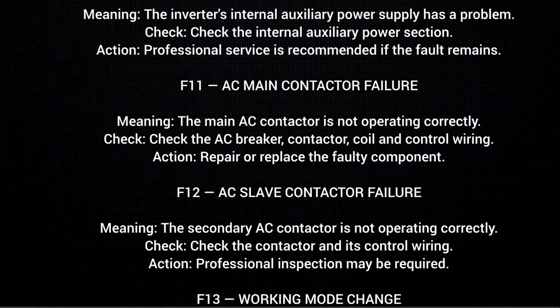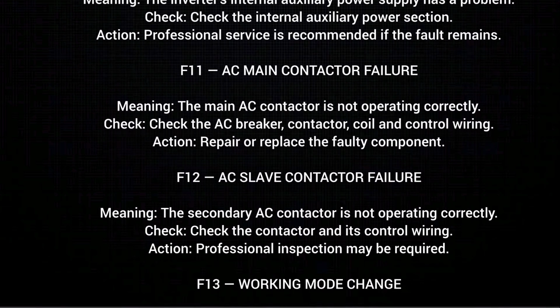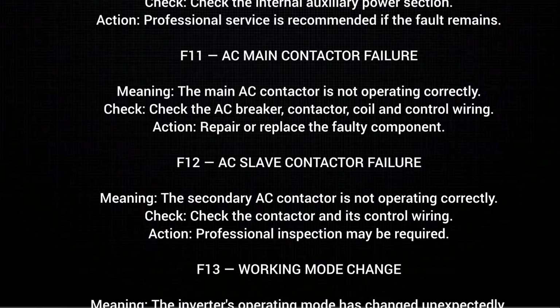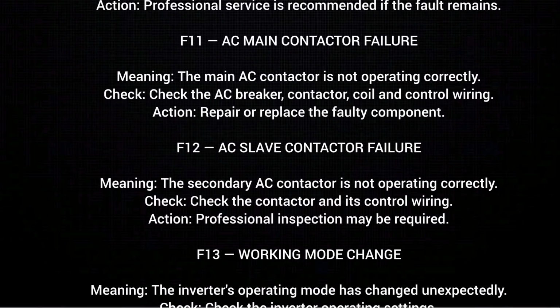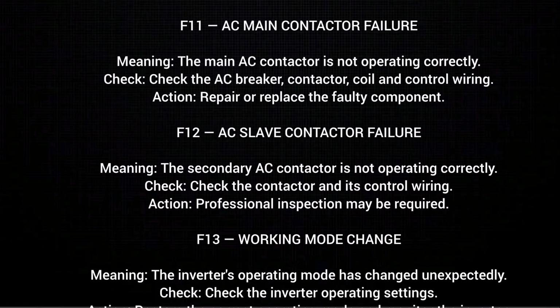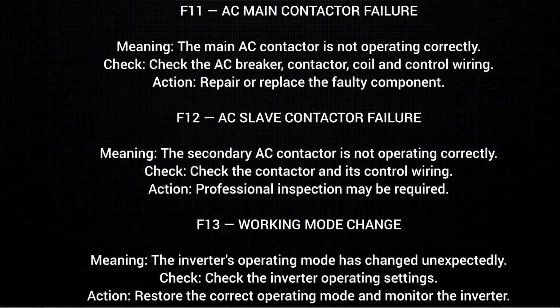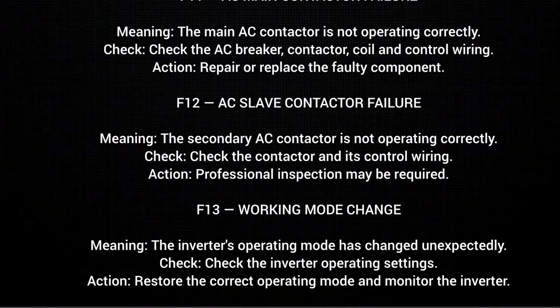F11 AC main contactor failure, meaning the main AC contactor is not operating correctly. Check. Check the AC breaker, contactor, coil and control wiring. Action. Repair or replace the faulty component.